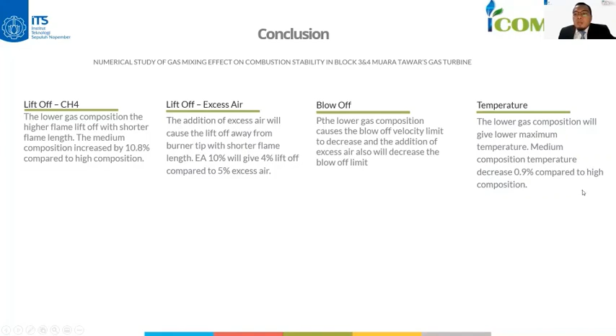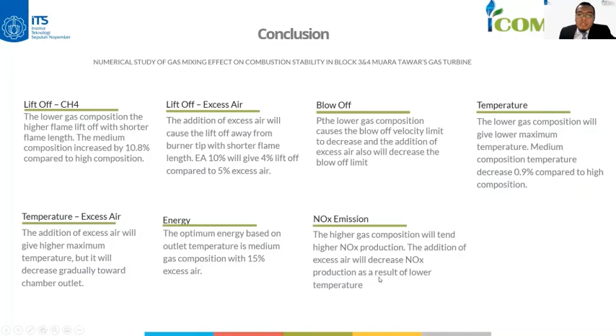The temperature: the lower gas composition will give a lower maximum temperature. Medium composition temperature decreases 0.9% compared to high composition. The excess air: the addition of excess air will give a higher maximum temperature, but it will decrease gradually toward the chamber outlet. The energy: the optimum energy based on outlet temperature is medium gas composition with 15% excess air. Lastly, NOx emission: the higher gas composition will tend to give higher NOx production. The addition of excess air will decrease NOx production as a result of lower temperature.